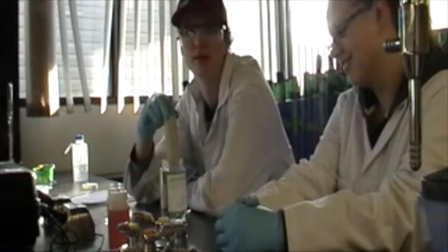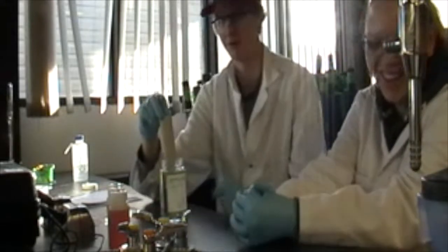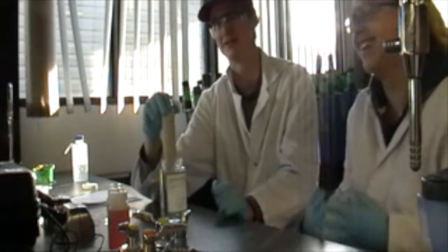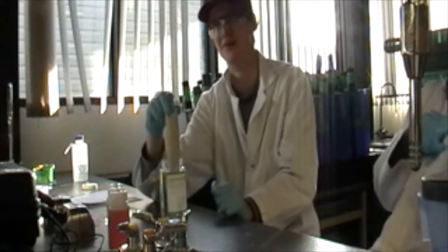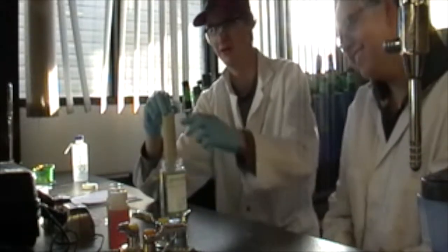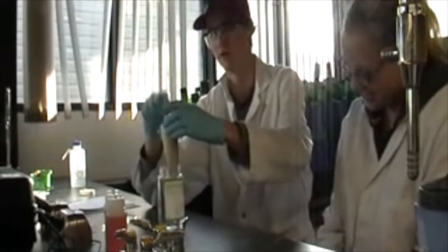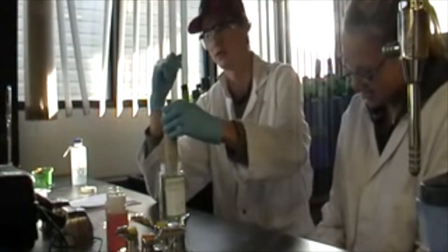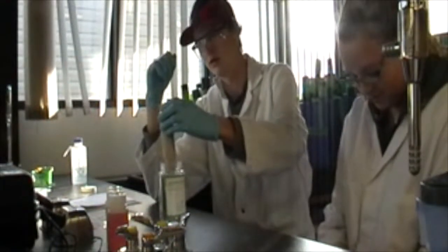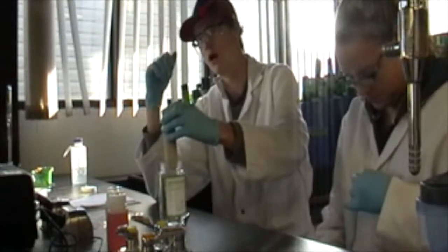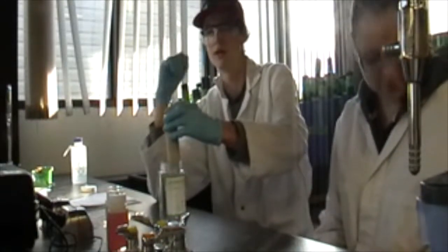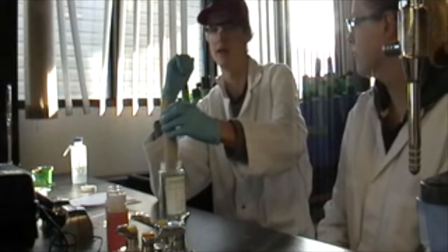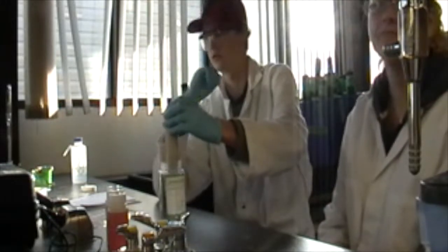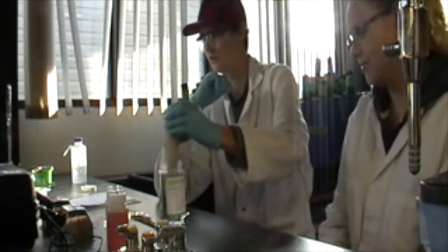Our battery died in our video camera, but we still got full battery in our pH meter. And we're at the step of reading our tap water after calibrating the instrument, triple rinsing our PET 500, and now we have a pH of 7.06 at 18.5 degrees Celsius, and that's for our tap water.